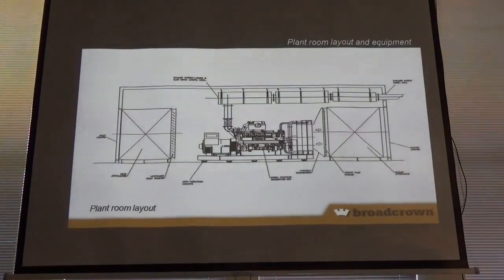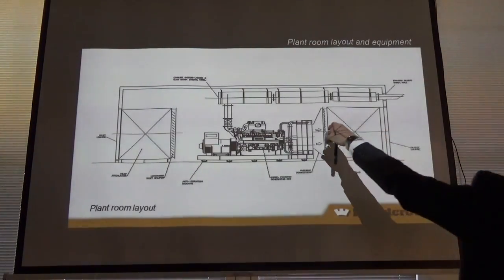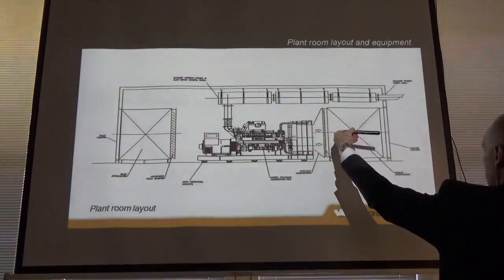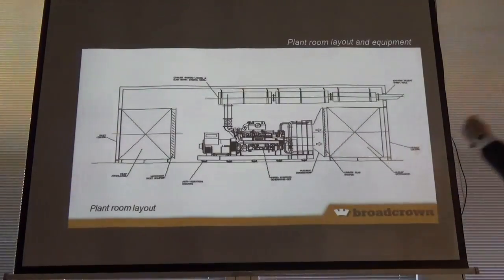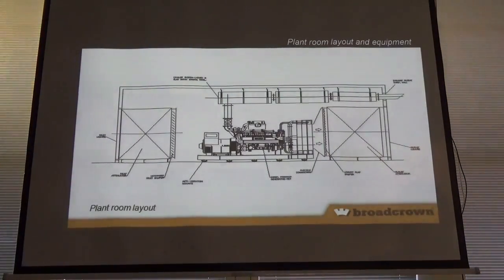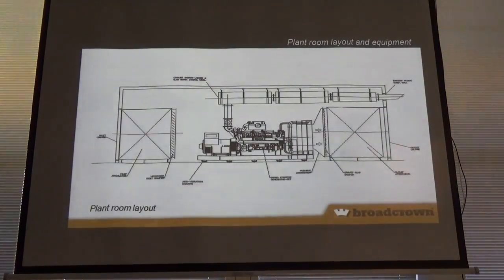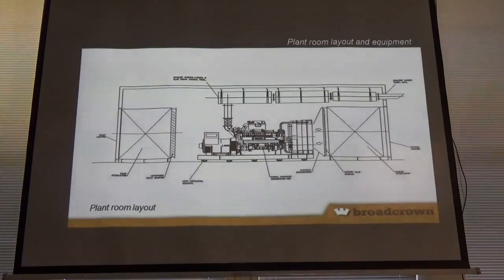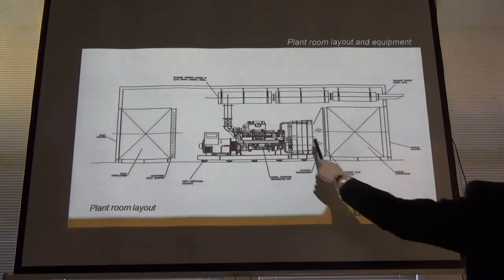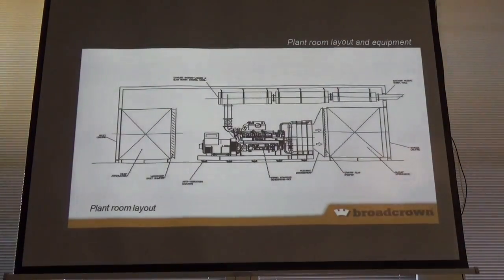Spring open, in other words, they'll fail open so the set can still run. Gravity dampers, basically they're just blown open by the airflow itself, and they'll sit. You get more of a pressure drop off that. So if you're talking more within limits of pressure drop, etc., you can have those spring open motor close as well. So again, keeping it within limits. Now, the performance criteria of the fan that's located there, often what happens when you put them in plant rooms, in fact I've drawn it.